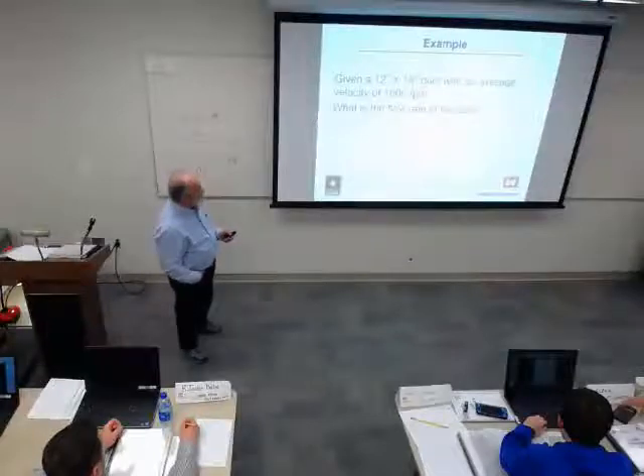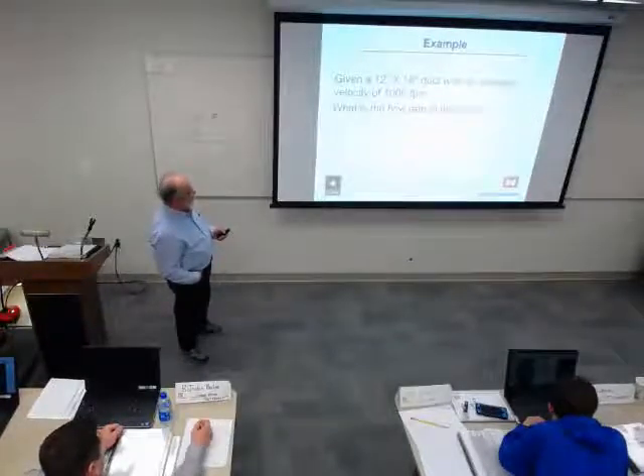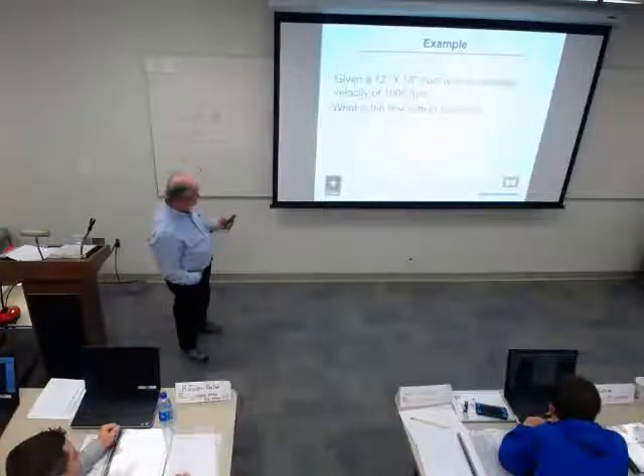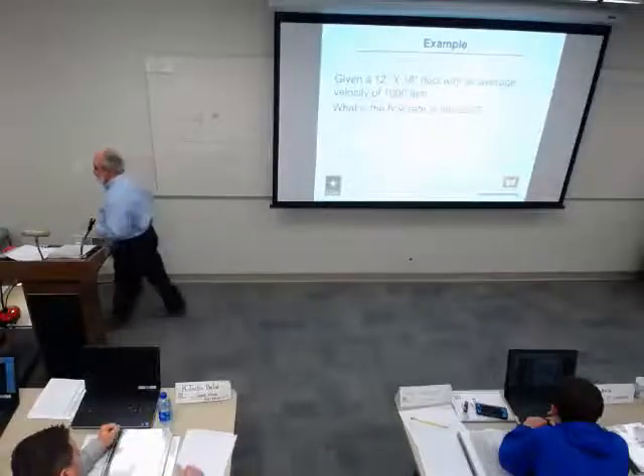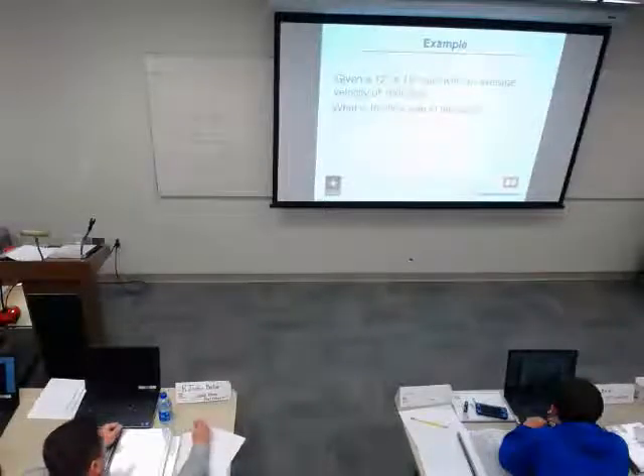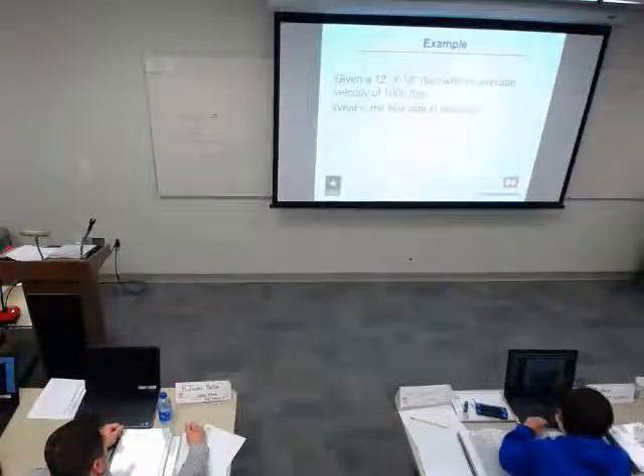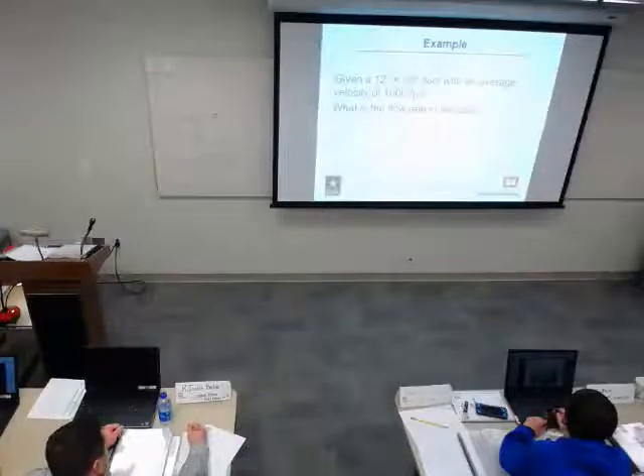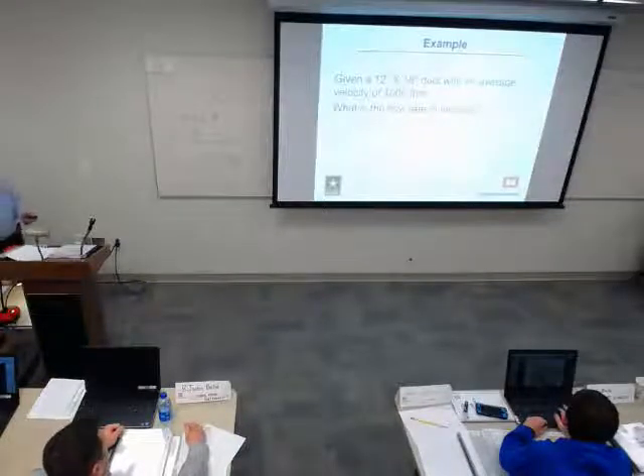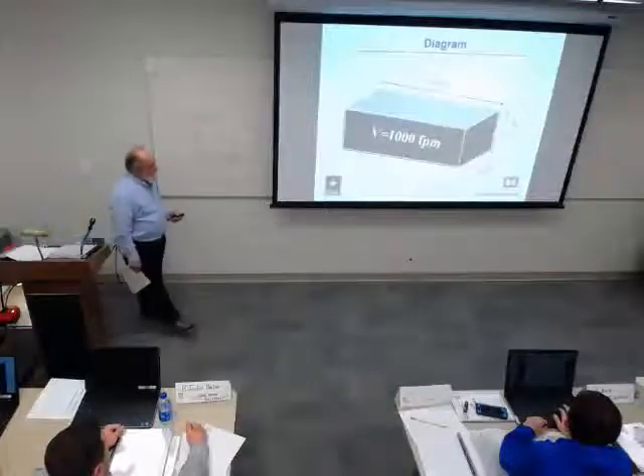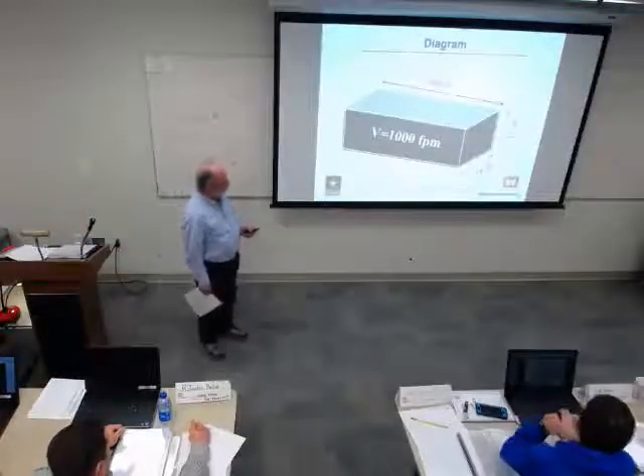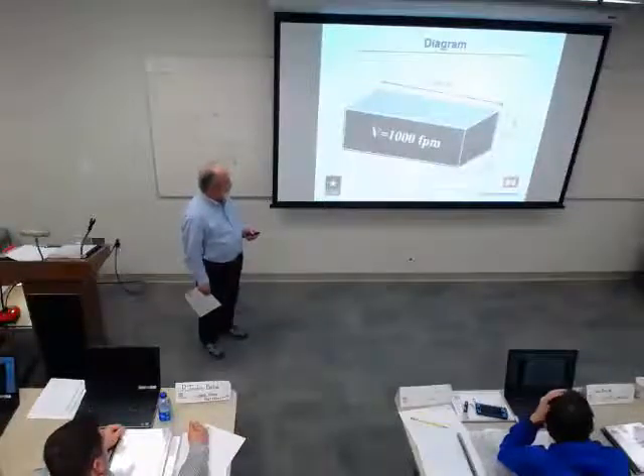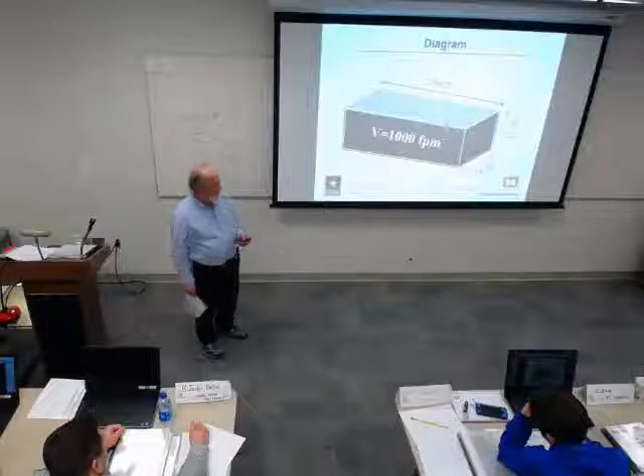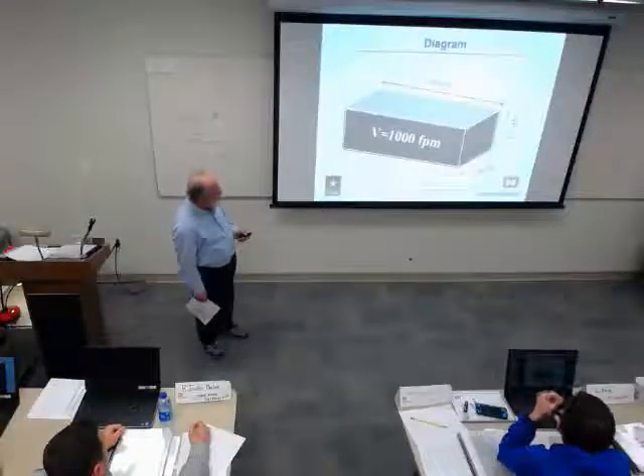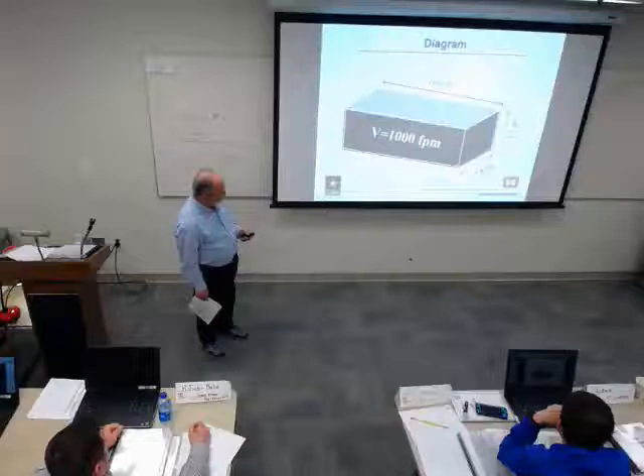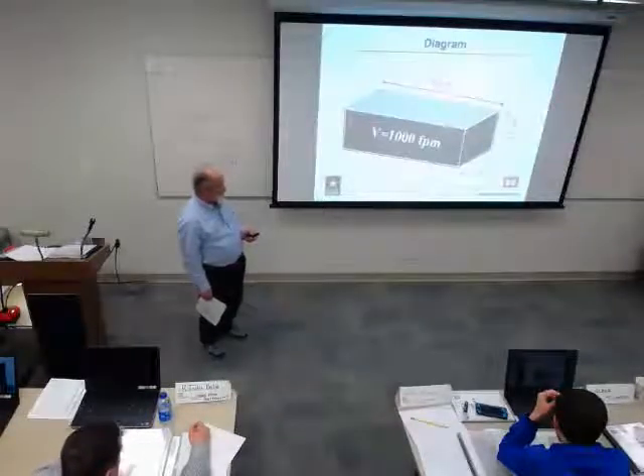So here we've got a 12-inch by 18-inch duct with an average velocity of 1,000 feet per minute. What's the flow rate in the duct? So I'm going to look at that slide in just a minute. Okay, so here we got air moving along, and we have a volume that we're moving. It's 1,000 feet in a minute. We've got 1,000 cubic feet of air moving through there. So there's our diagram. And our duct, the opening right there that we're looking at, is 18 inches by 12 inches.